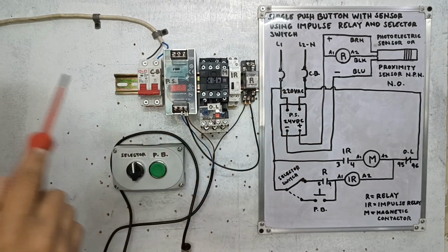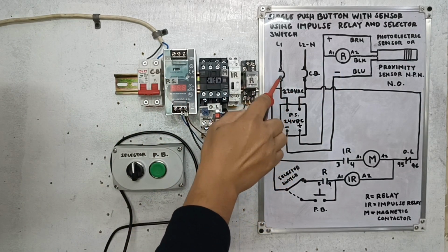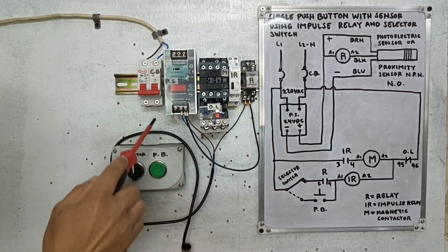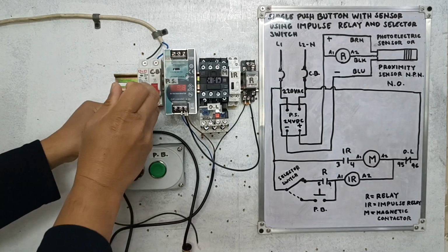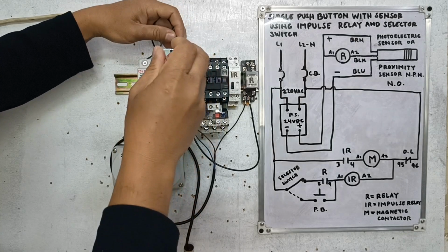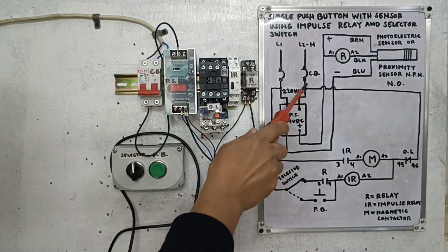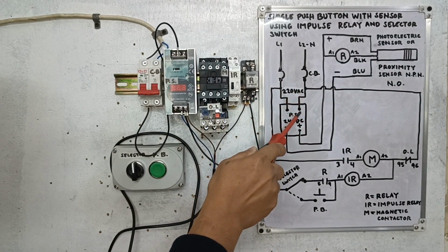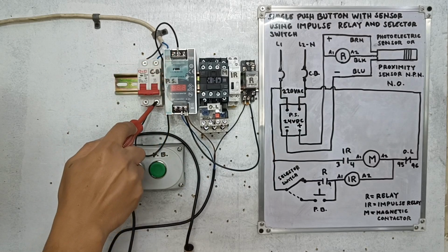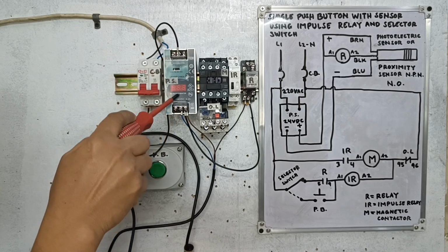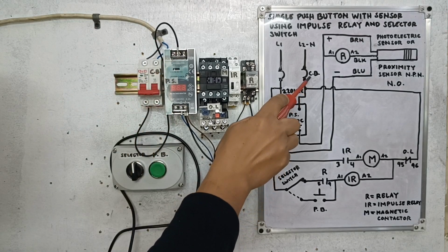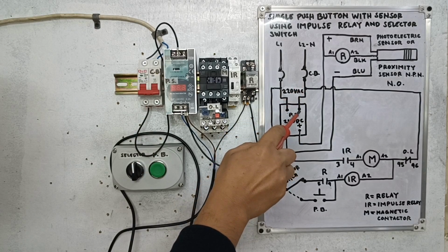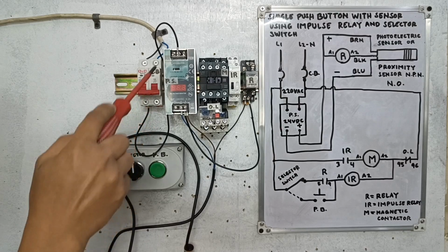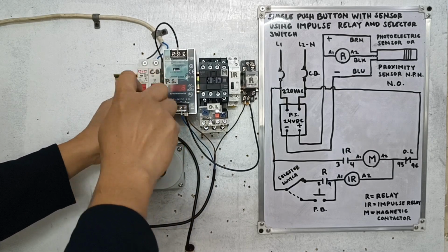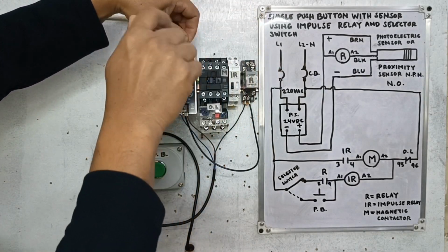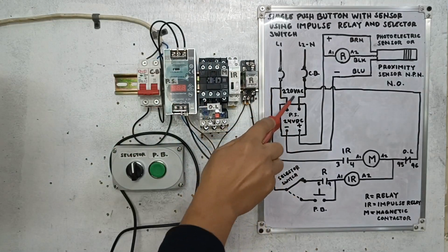Okay, now we have finished the sensor connection to the relay. Now the next, guys, we're going to connect our power supply. From the load side of the circuit breaker, we put here, from here to here. The next, from the load side of the circuit breaker, going from here to here. This is our power supply, guys, 220 volts in order to give 24 volts DC. So from the load side of the circuit breaker, going from here to the input of our power supply, from here to here. We have already finished this connection.